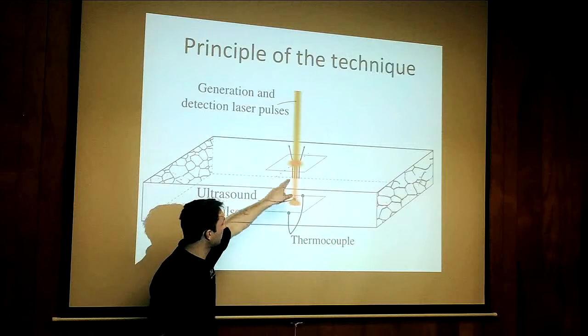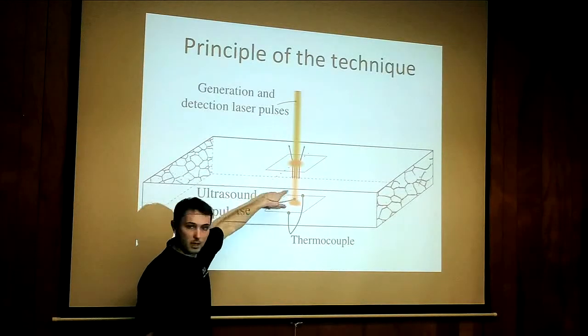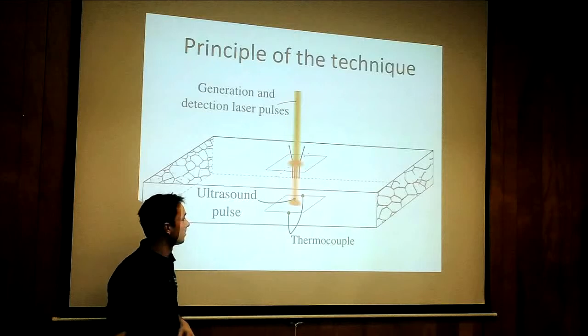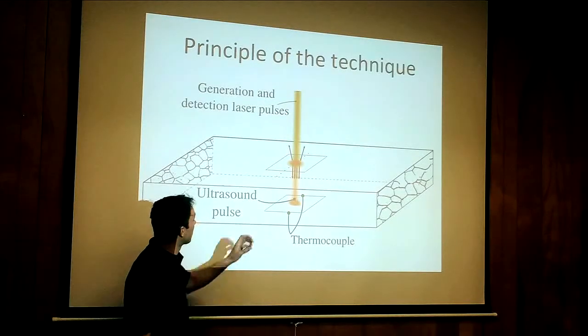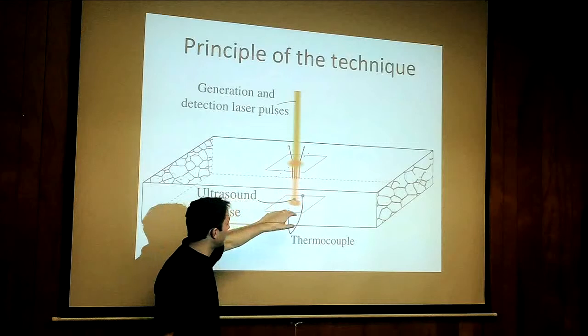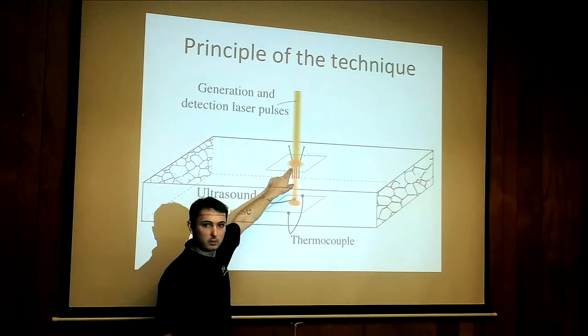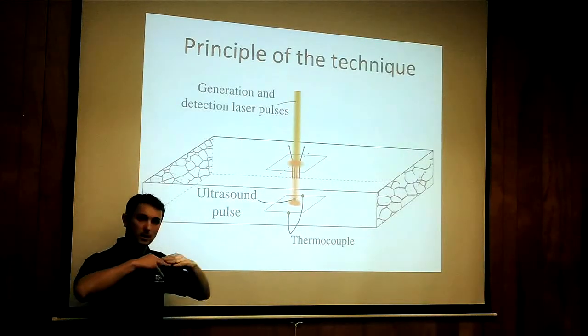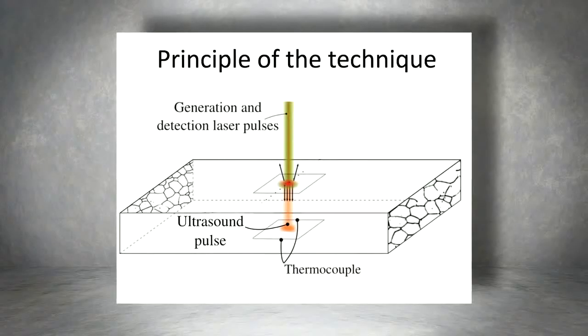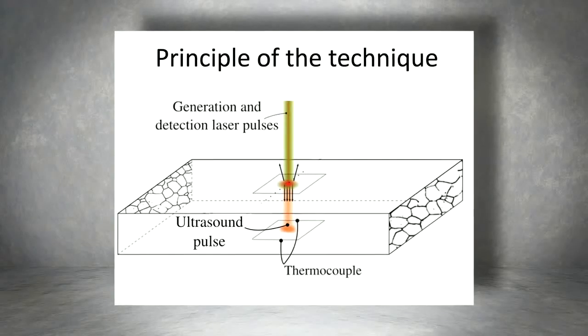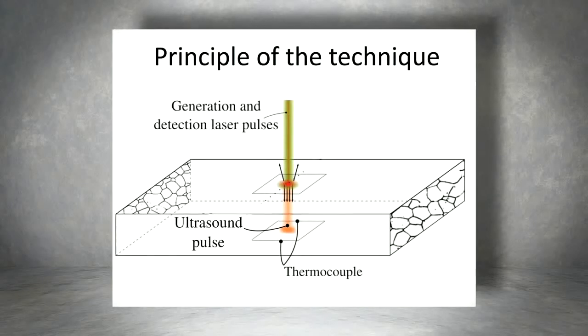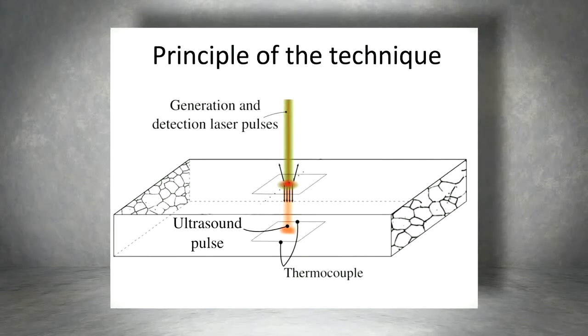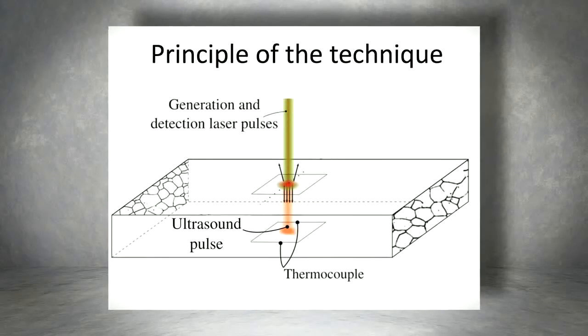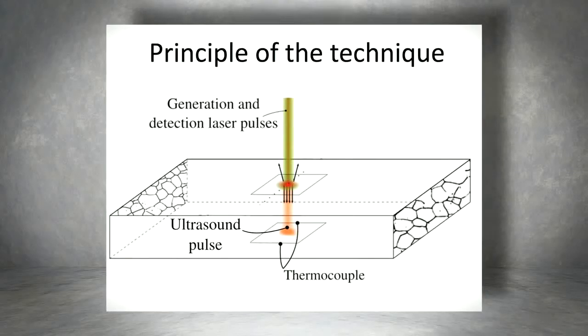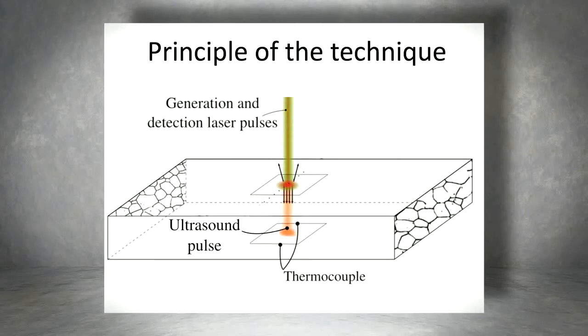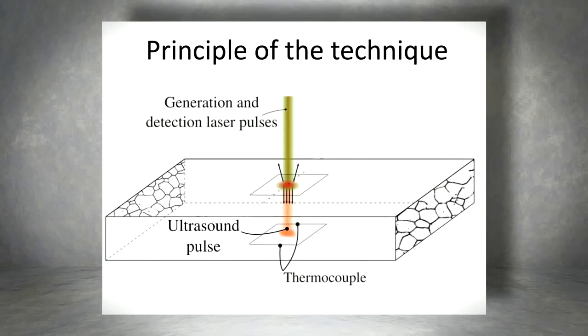This pressure wave, represented in red, bounces back and forth between the two surfaces of the sample. A second laser is looking at the sample, and each time this wave comes back to the generation surface, there is a tiny microscopic displacement that affects the light of this detection laser. This reflected light is collected in the probe, and thanks to an interferometer, we can access a signal proportional to the surface displacement measured at the generation surface.